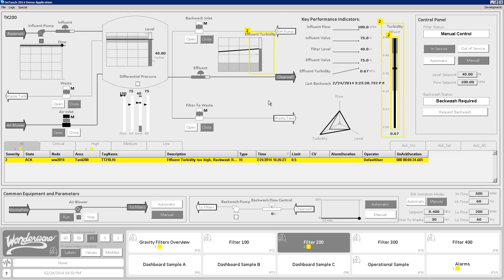You can clearly see there's something wrong with the effluent turbidity of this unit — I need to do something. Other things that can be done here are consistent color usage. We've applied this so that 'on' is always this shade of gray and 'off' is intended to be white. Whether it's a button that says in service or out of service, the in-service state is the darker one — there's a consistent use of color.